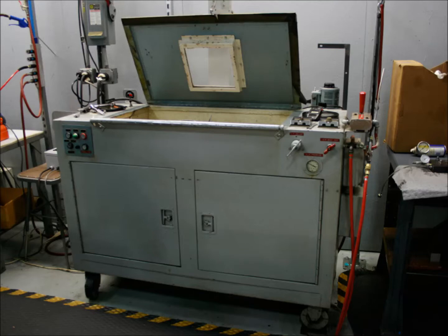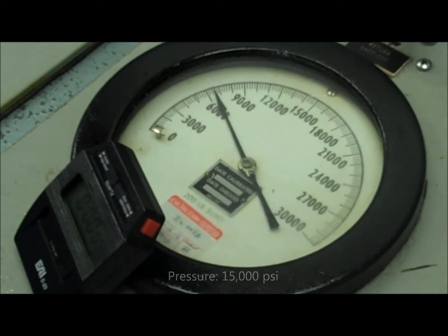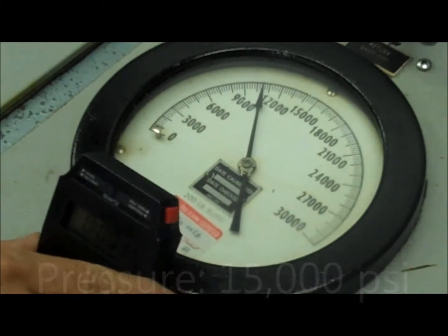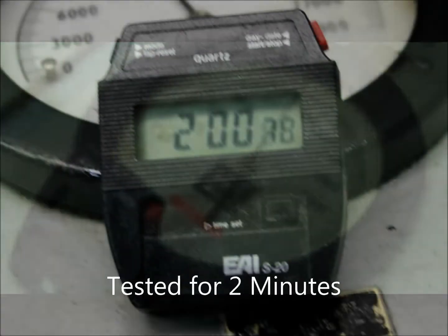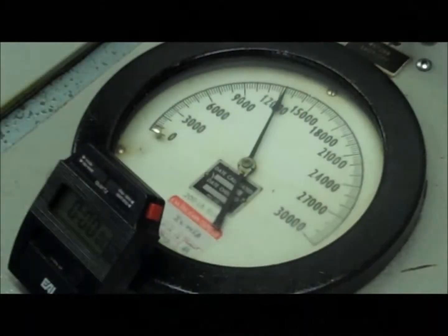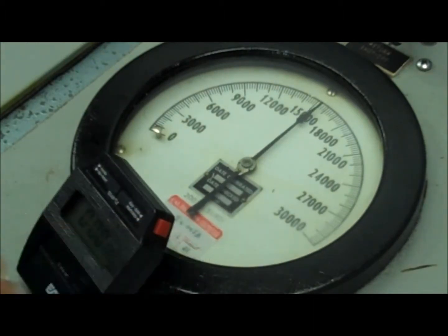We attach it to another fitting and do a static test. We build the pressure up to 15,000 psi and hold it for two minutes and check it for any kinds of leaks. If it leaks, we have to eliminate the hose, either make it a shorter hose or start all over. As you can see here, we're now at 15,000 psi and the stopwatch has started and we'll hold this for two minutes.